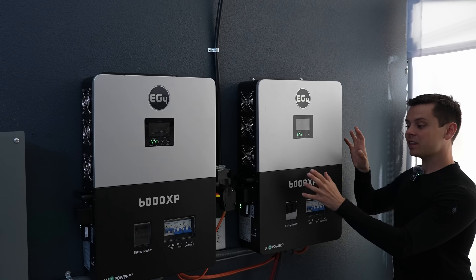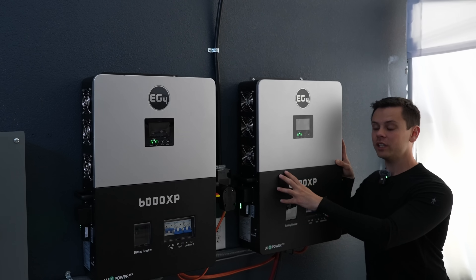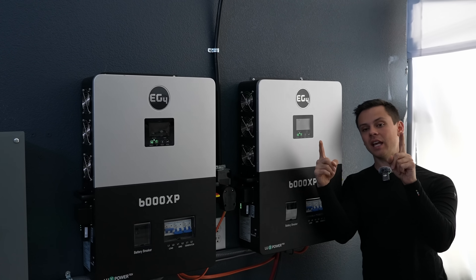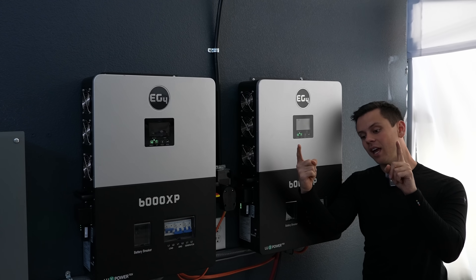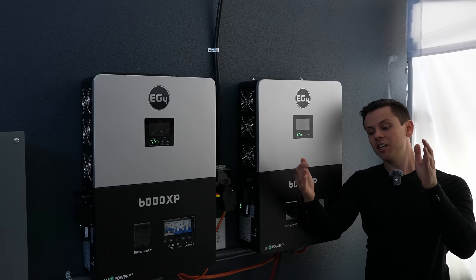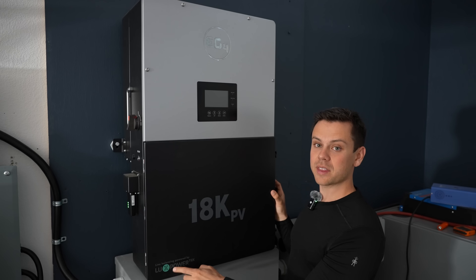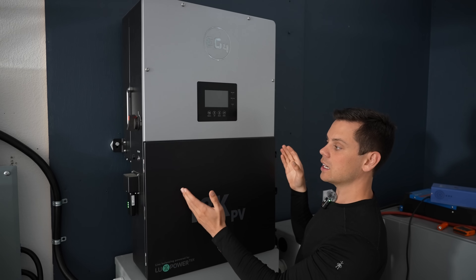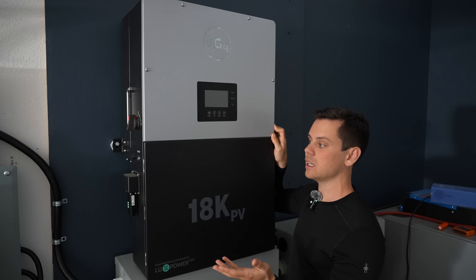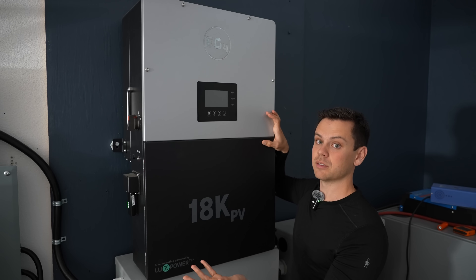When it comes to line imbalance with the 6000 XP in parallel, you can only do 6,000 watts per leg on its split-phase output. On hybrid inverters, they have line balancing — so you can put a larger imbalance on Sol-Ark and 18K PVs. With LuxPower, their line balancing technology can get up to 8,000 watts on each leg, which is similar to the new Sol-Ark with its recent update. So hybrid inverters have a better capacity for line imbalance compared to off-grid specific inverters.